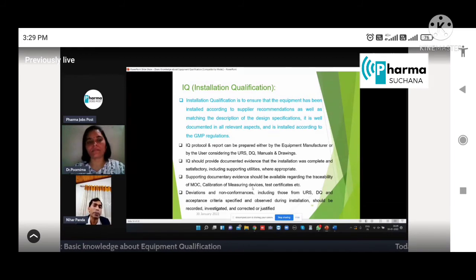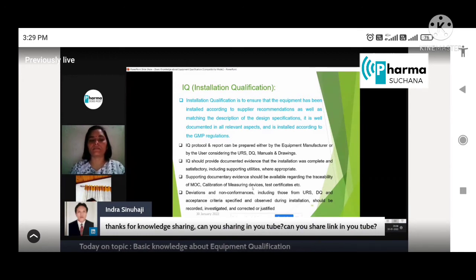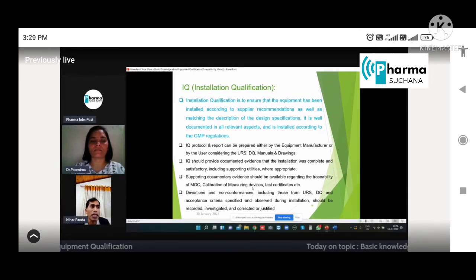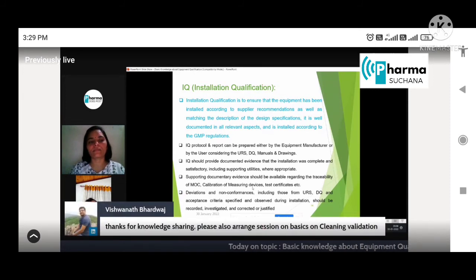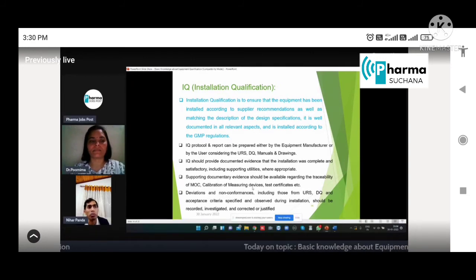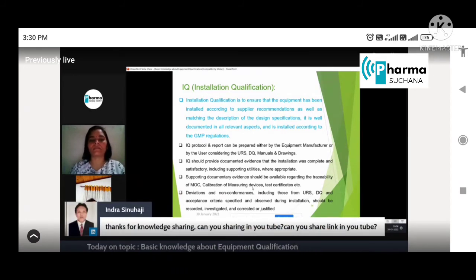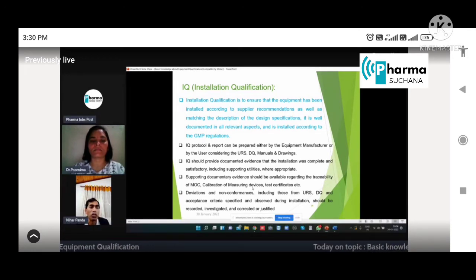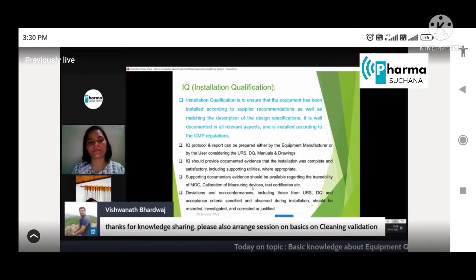Next is IQ, Installation Qualification. Installation Qualification is to ensure that the equipment has been installed according to supplier recommendation as well as matching the description of the design specifications. It is well documented in all relevant aspects and is installed according to the GMP regulations.